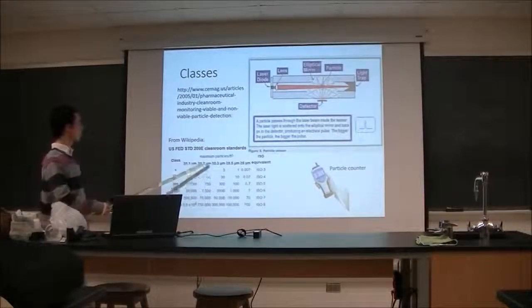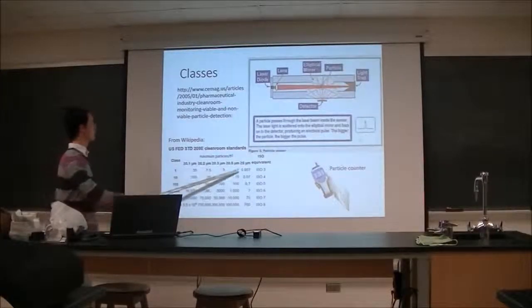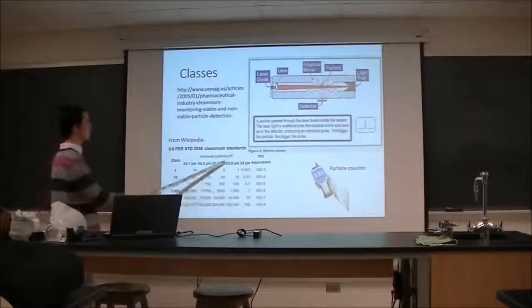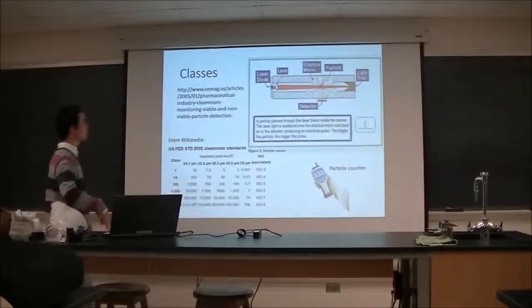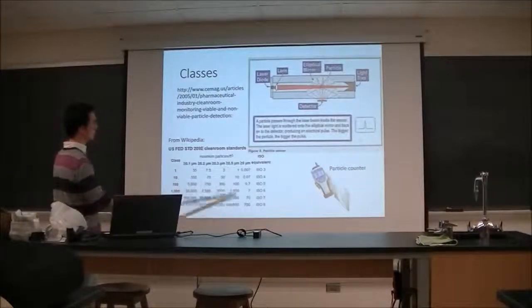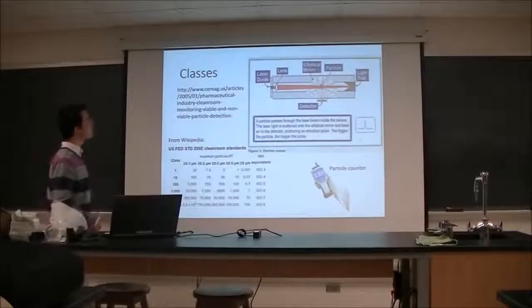So the more particles, the dirtier the clean room. The higher the class number, the worse the clean room. So this would be the good one. And what you verify to classify the class is the 0.5 micrometer particles. So this is simply the number of particles per cubic foot.